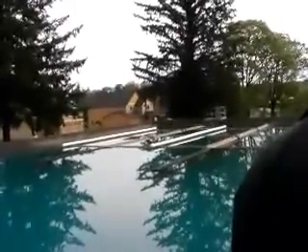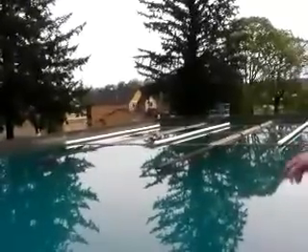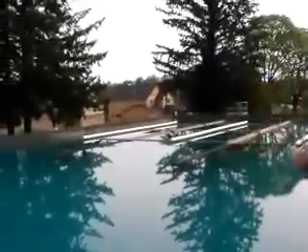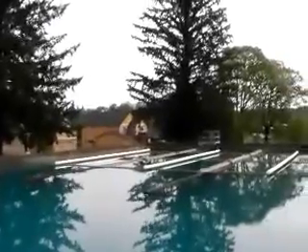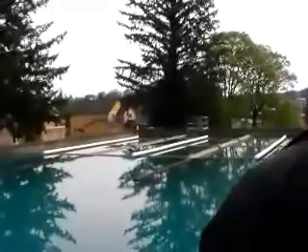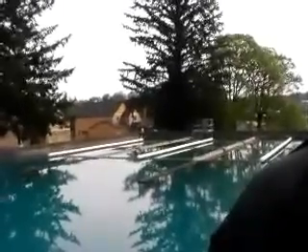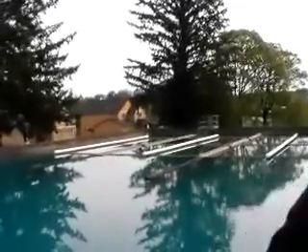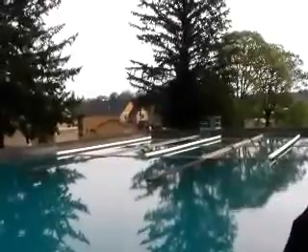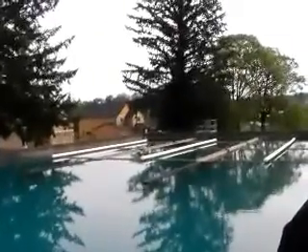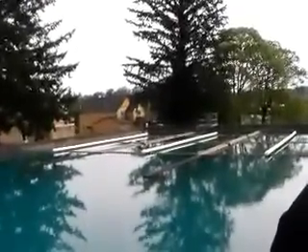I'm sitting here watching it, looking at it, thinking, okay, first I thought that it was coming from this side, coming this way, but it wasn't. Apparently it's in the water. I don't know how, but it was shaking. It was ripping out bolts. Stainless steel bolts that actually ripped out the concrete, 6 inches of concrete, just tore it right out. We had to fix it with other stainless steel bracket collars to hold it in place.